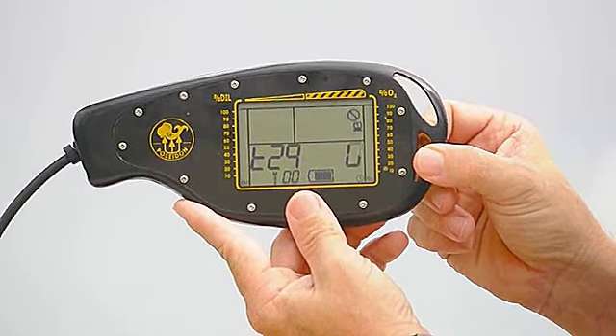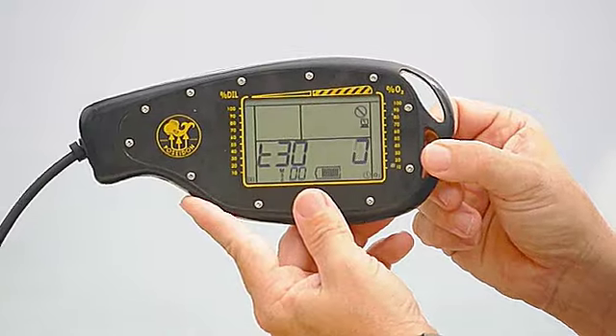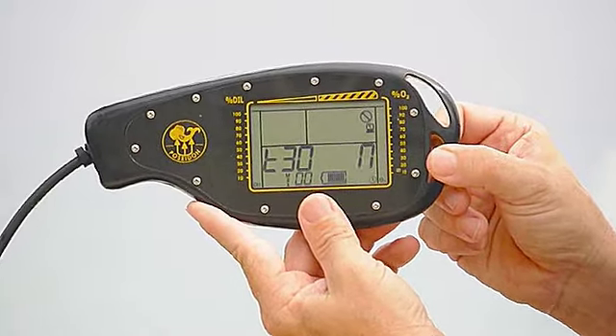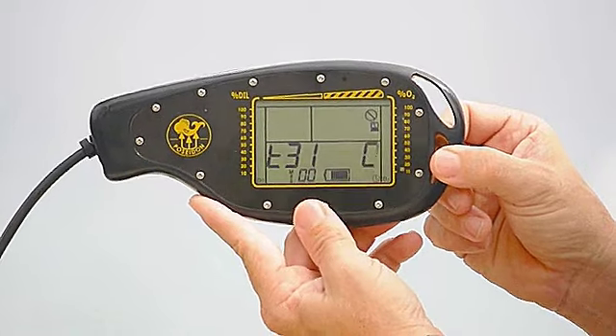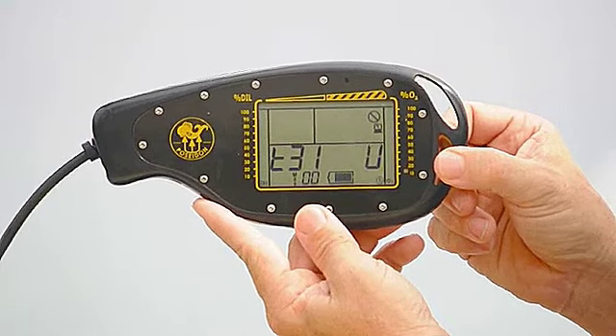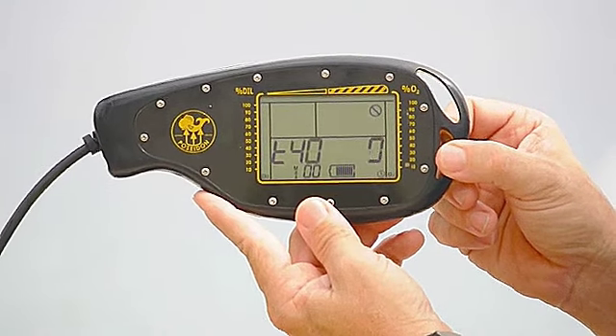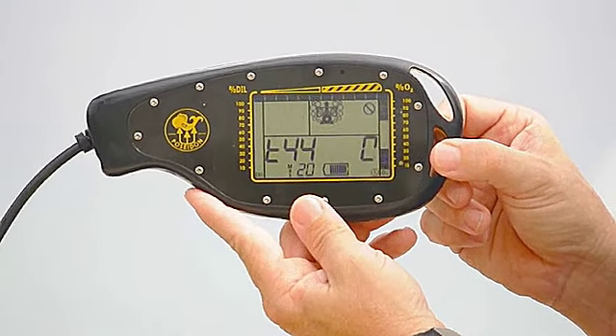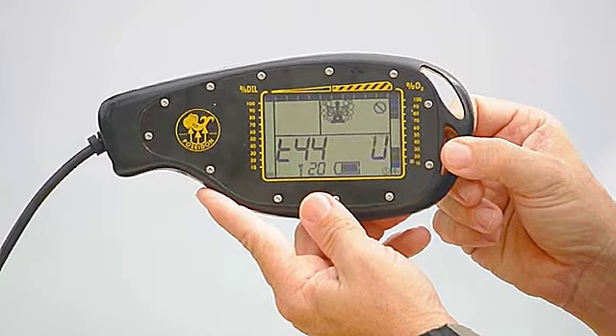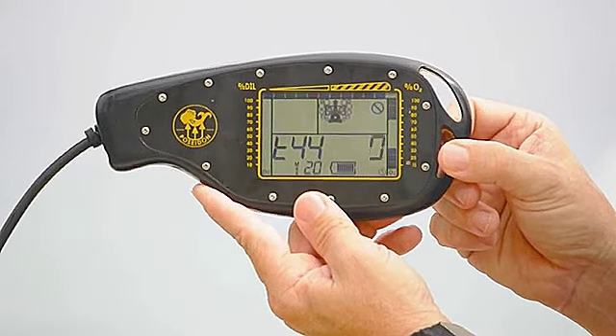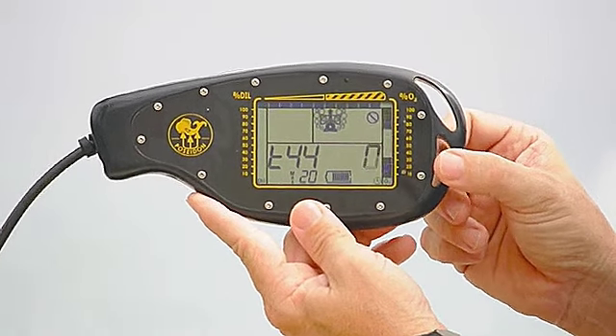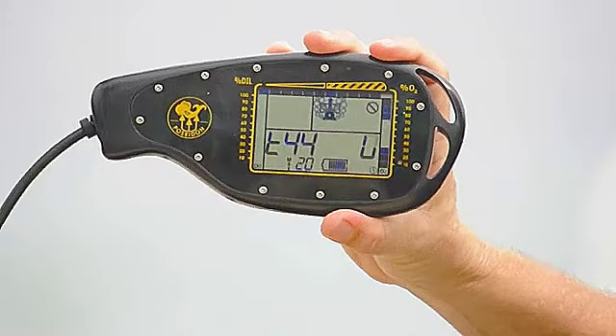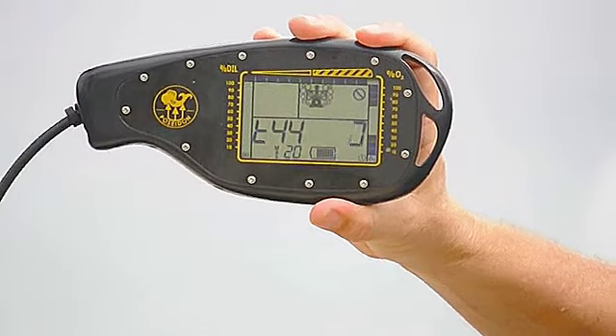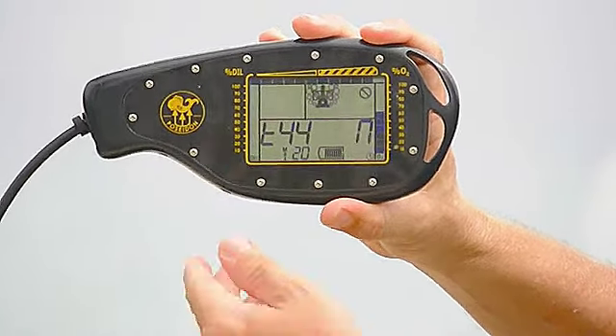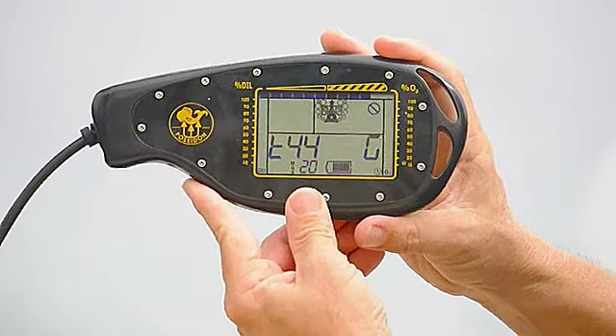As it goes through the tests, it runs through a different series of other tests. It makes sure that the mouthpiece position can be detected both in open circuit and closed circuit. It makes sure that there's gas in the cylinders. It runs a check on the positive pressure loop test so that it fills the loop up. It has a depth sensor inside the breathing loop so it can detect whether or not there's pressure in the system and whether or not it can hold that pressure, so it does an automatic loop test.